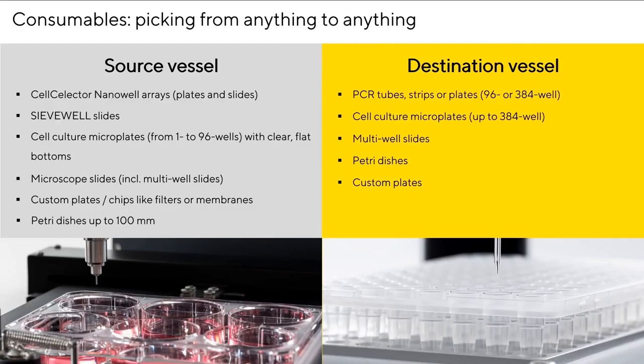When looking closer at the picking modules, the system can be equipped with a semi-solid picking module that takes advantage of disposable tips, an adherent colony picking module using reusable stainless steel tips, and a single cell picking module using glass capillaries, which is the most versatile picking module. Once the picking module is installed, it is automatically recognized and all corresponding picking protocols are loaded within the software. CellCelector Flex allows picking from almost anything to anything. As a source vessel, we can use nano well arrays, cell culture microplates with clear flat bottoms, microscope slides, petri dishes, and even custom plates. We can deposit material in cell culture microplates, multi-well slides, petri dishes, and even PCR tubes, strips, or plates.